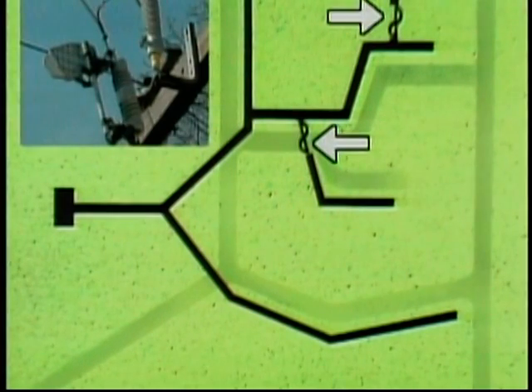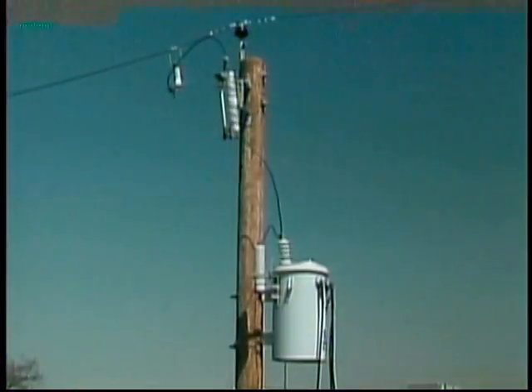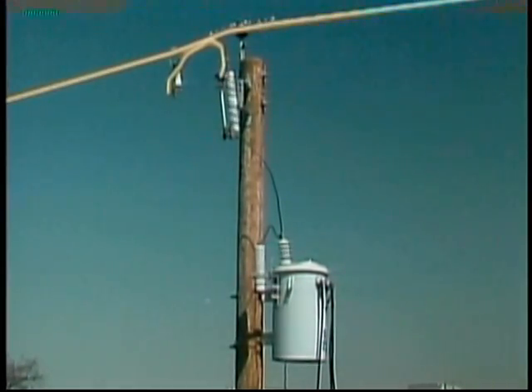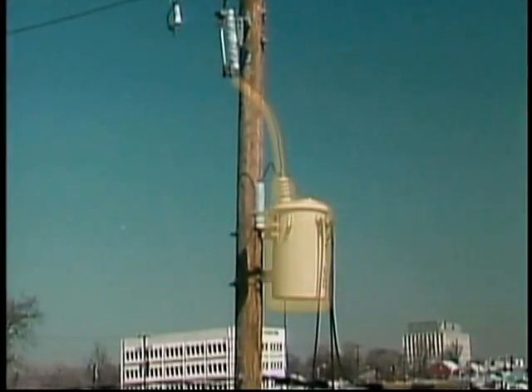Fused cutouts can be used in a lot of places. They may be used where laterals or branch lines are tapped off a circuit. In this application, they would typically be coordinated with any sectionalizers and reclosers on the circuit. Fused cutouts may also be used in the circuit connections of distribution equipment to protect the equipment from excessive current from the line and to protect the line from excessive current from the equipment.